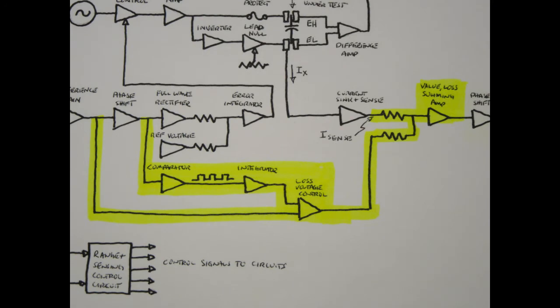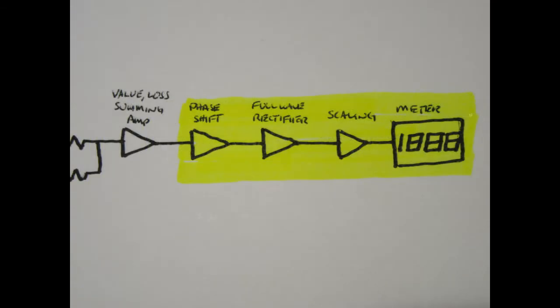The meter circuit includes a subsection that taps off the excitation voltage and shifts it by 90 degrees in phase, referred to in the diagram as the loss voltage control signal, and then sums it with the value and loss summing amplifier with the I-sense signal coming from the current-sense amplifier, thus cancelling the non-reactive part of the measured impedance signal, and leaving only the reactive signal that represents the capacitance being measured. The resulting signal passes through additional stages to rectify the AC signal to a DC signal, and scale it to a range that the actual meter is able to display.